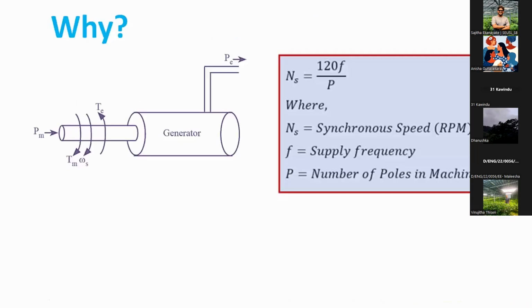This will explain how it is happening actually. You might already know the synchronous generator. Basically, if you consider the rotor, there you have two torques: one is the mechanical torque, the other is the electrical torque. Mechanical torque is the one you apply using a turbine. The electrical torque is the one applied because of the current flow through the stator. So if the mechanical torque is higher than the electrical torque, what will happen?